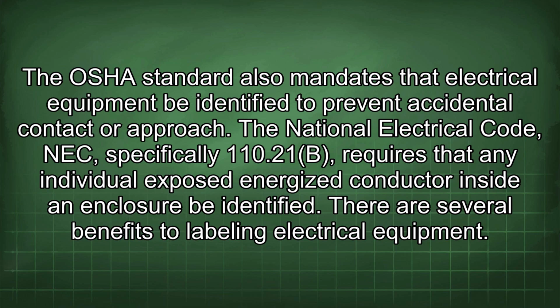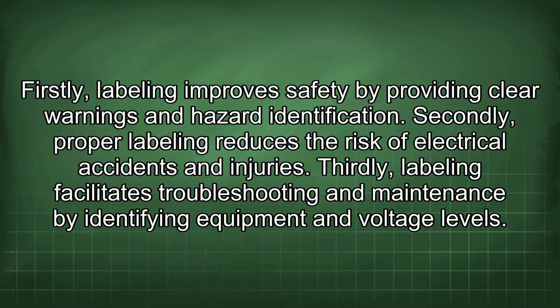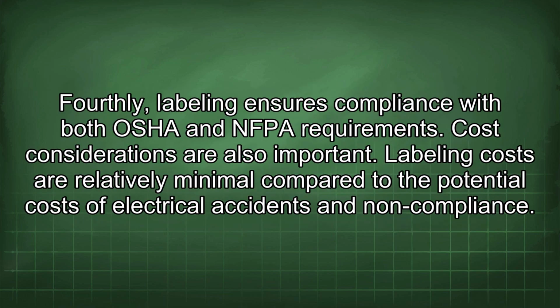The National Electrical Code, NEC, specifically 110.21(b), requires that any individual exposed energized conductor inside an enclosure be identified. There are several benefits to labeling electrical equipment. Firstly, labeling improves safety by providing clear warnings and hazard identification. Secondly, proper labeling reduces the risk of electrical accidents and injuries. Thirdly, labeling facilitates troubleshooting and maintenance by identifying equipment and voltage levels. Fourthly, labeling ensures compliance with both OSHA and NFPA requirements.